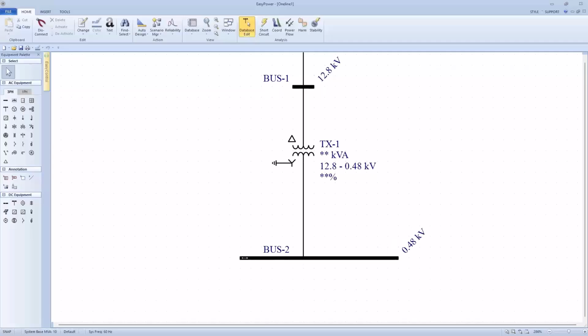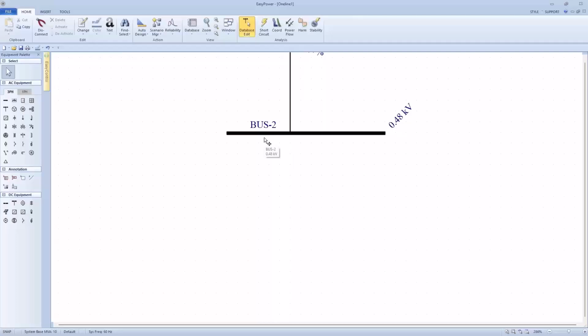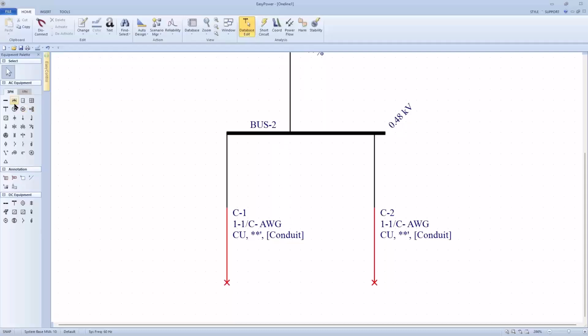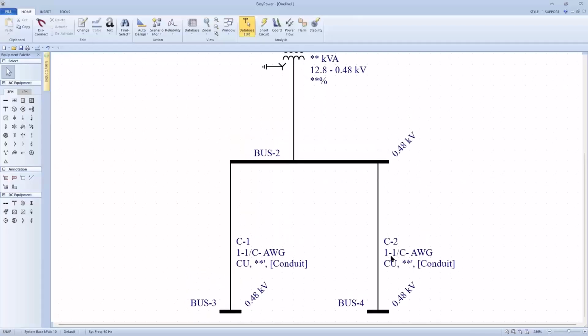He said extend this bus about half the width of the screen and drop a cable on each side. The cable is a circle with 3 inscribed circles on the equipment palette. I'm going to left click and pick it up, put the crosshairs on the bus, left click again, do the same thing on the other side. Now he said terminate each cable with a plain bus. So I'm going to reuse the icon. I'm going to pick up the plain bus, hold down control, and then I can put a bus on the end of the cable.